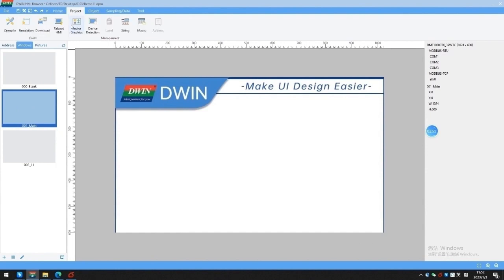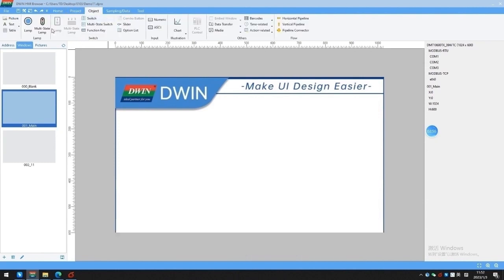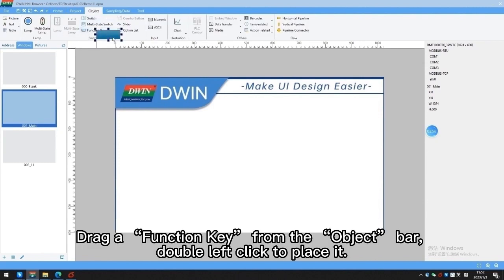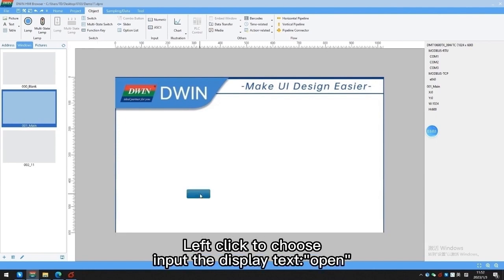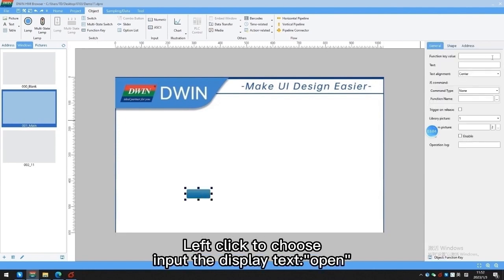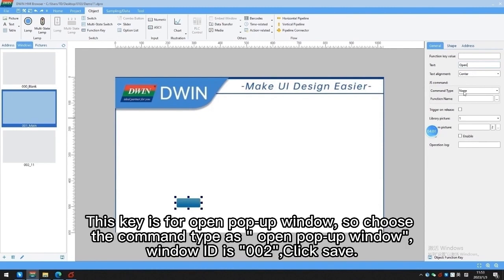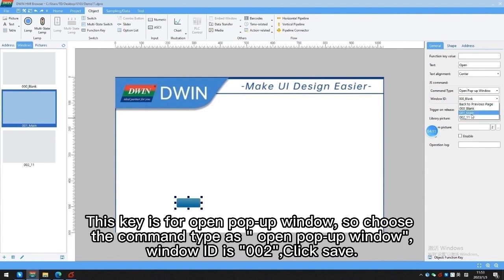Next, I will introduce the simple use of function key, lamp, and switch. Drag a function key from the object bar and double left-click to place it. Input the display text as Open. This key is for opening a pop-up window, so choose the command type as Open Pop-up Window with window ID 002. Click Save.